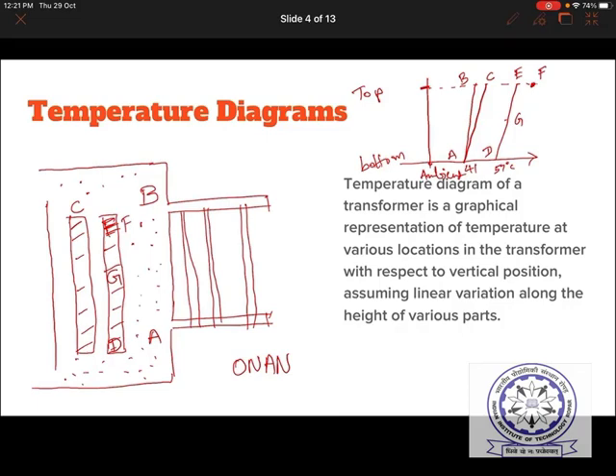A is around 41 degrees centigrade, you can see from the graph, and B is around 53 degrees centigrade. This is in oil. So among all these points, A and B are relatively on the lower side, and C is also in oil, but you can see from B to C there is a certain distance, and C is expected to be at a higher temperature, typically 57 degrees centigrade. This is for ONAN, and I am drawing.